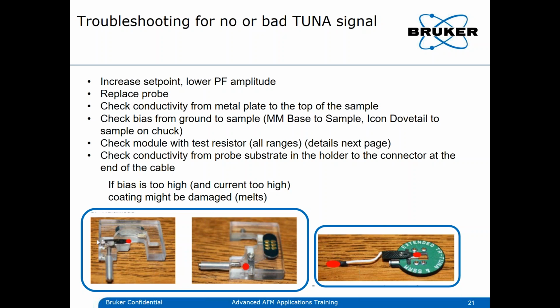And here's the holder for the multimode on the left-hand side. You would measure here also from the tip holder to the back side of the holder, where this usually is the cable connector. Sometimes, and this is for the multimode only, there comes with the multimode also a small metal shield, which basically would shield out any stray field. You would make your multimode head a Faraday cage. And basically, with this metallic sheet, you can shut out all electrical fields completely, so that nothing is interfering from outside with your optical head from the multimode.